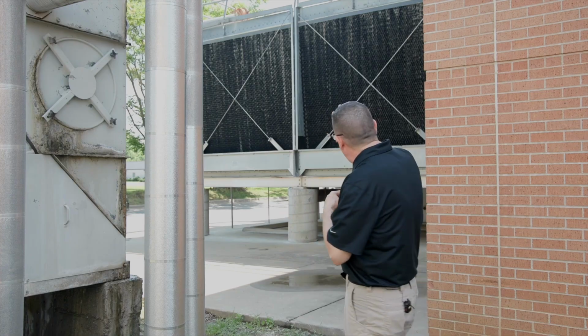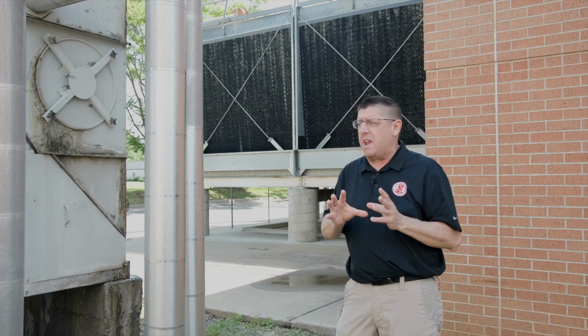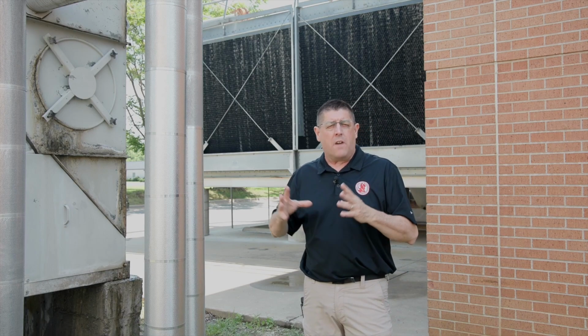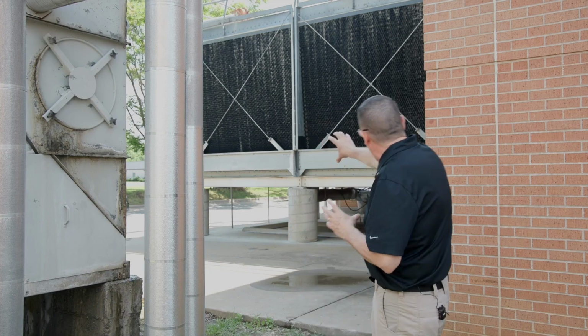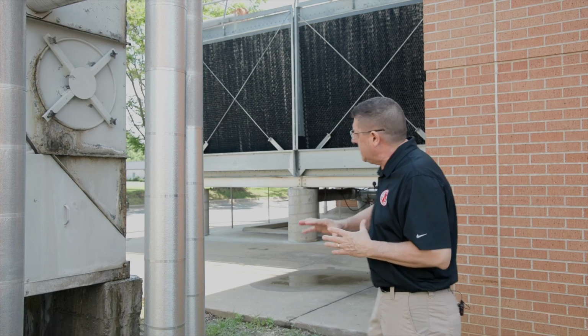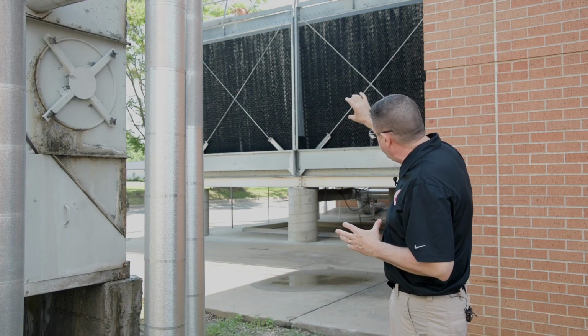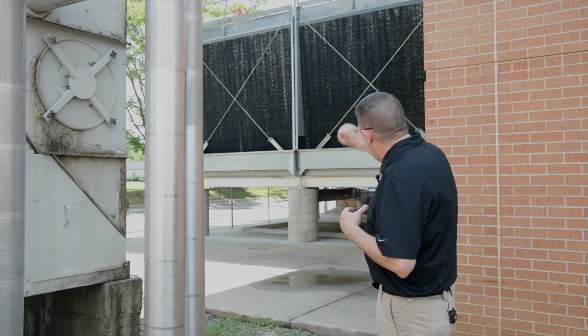If I walk underneath this cooling tower and see water leaking, that's a sure sign that something's going on. If I look at the tub, that horizontal portion of the steel, and see it calcified, that's water leakage. Then I'll look at those cells, those individual little honeycombs—as you can see, we've got some calcification going on in there. There's a maintenance schedule that should involve cleaning those cells to get some useful life out of that.